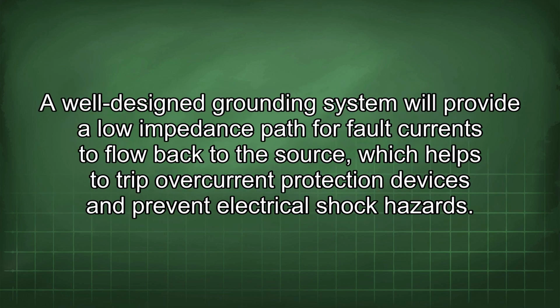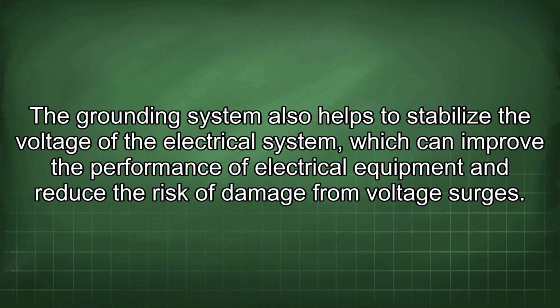A well-designed grounding system will provide a low impedance path for fault currents to flow back to the source, which helps to trip overcurrent protection devices and prevent electrical shock hazards. The grounding system also helps to stabilize the voltage of the electrical system, which can improve the performance of electrical equipment and reduce the risk of damage from voltage surges.